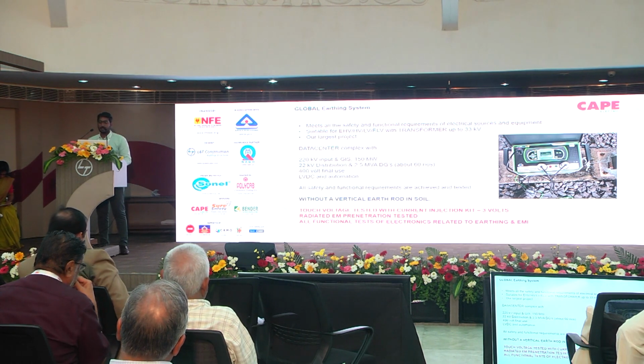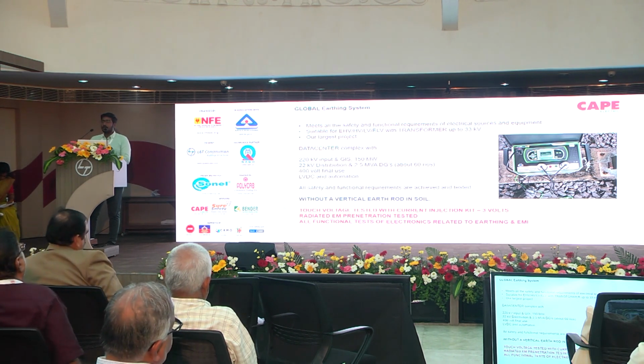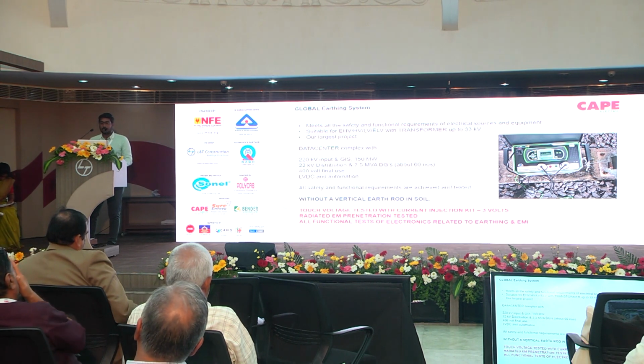Next, another major topic which needs to be told here is the global earthing system. The global earthing system meets all the safety and functional requirements of electrical source and equipment, and is suitable for HV, EHV, LV, ELV, and transformers up to 33 kV. Actually, this is the most important concern in the data center sector, where a data center complex starts from a 220 kV input and a GIS substation of about 150 megawatt, and from that 22 kV distribution and 2.5 megawatt DGs, approximately 16 numbers.